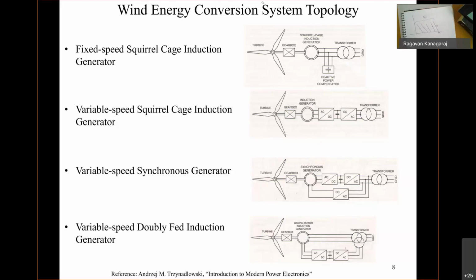Now we can go to the third scheme. In the third scheme, you have to provide field in the rotor winding, whatever field winding you have, and the stator will give the power. Once again, this is also called variable speed - whenever you put the frequency converter, that's called variable speed. Is that okay? So the third one is easy.